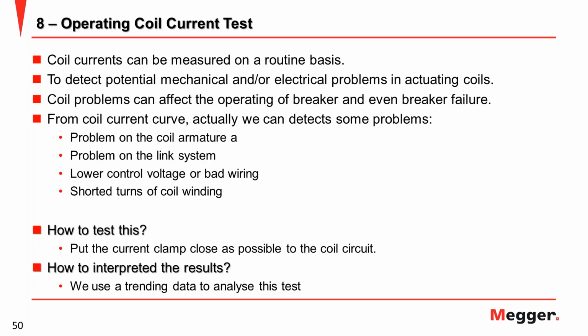Operating current test, the next test, is also important because the coil current test also gives you information about problems on the coil armature, problems on the link, lower control voltage or bad wiring, short turn of coil winding. So from the coil current trace, you can define more specifically where the problem comes from. This is why the coil current can be measured on a routine test. Mostly you can see this test together with the breaker timing test.